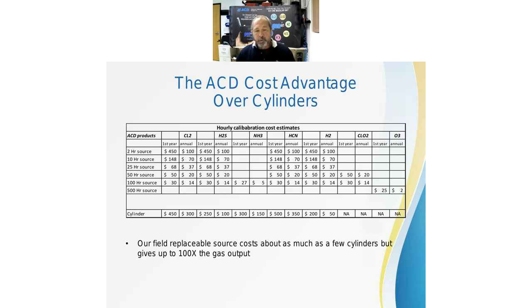So if you purchase one of these instruments, the upfront cost is more than, say, a cylinder gas or a permeation tube, but the cost per calibration is much lower once one of these instruments and generating sources has been purchased. So one generating source can produce as much gas as up to 100 58-liter cylinders. So they're very cost effective once purchased.